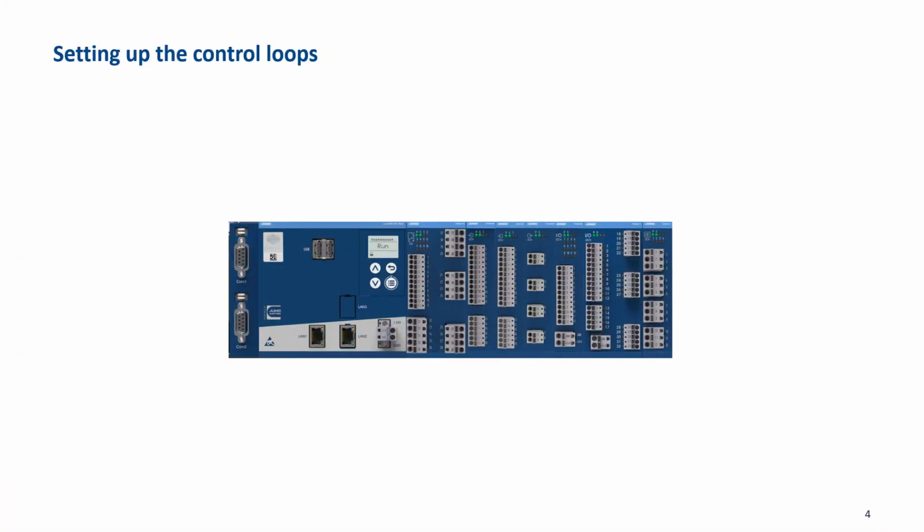First, I configure the settings for the control loops in Smartware Setup. I measure the temperature with a PT100 and 3-wire circuit. A continuous controller is used, and the actuator is controlled via a 4 to 20 mA signal. The humidity is available as a 4 to 20 mA signal. The controller also operates continuously, and the humidifier is controlled by a 4 to 20 mA signal.